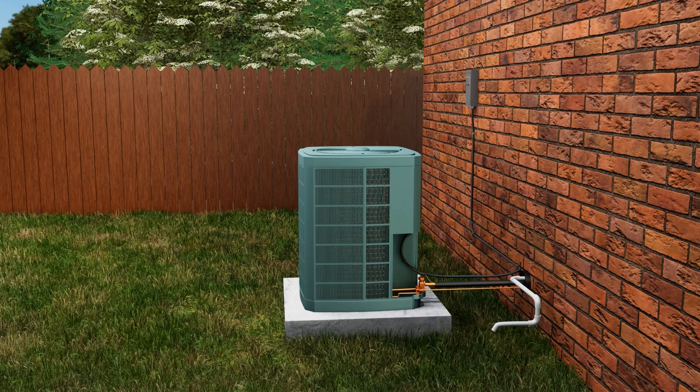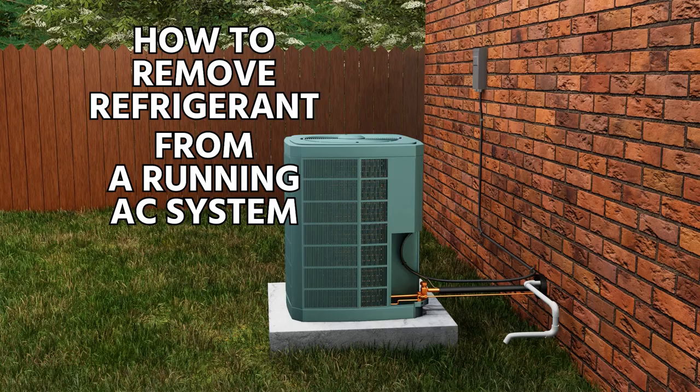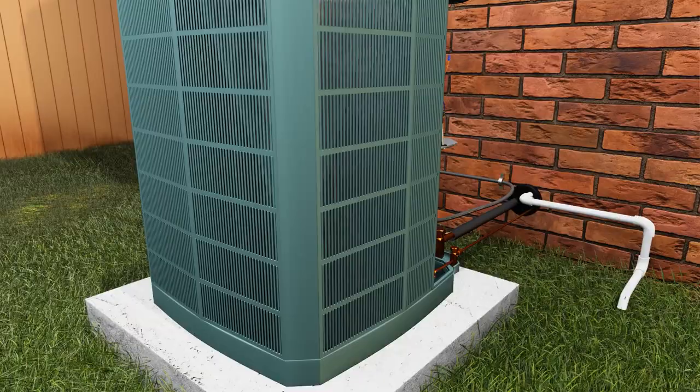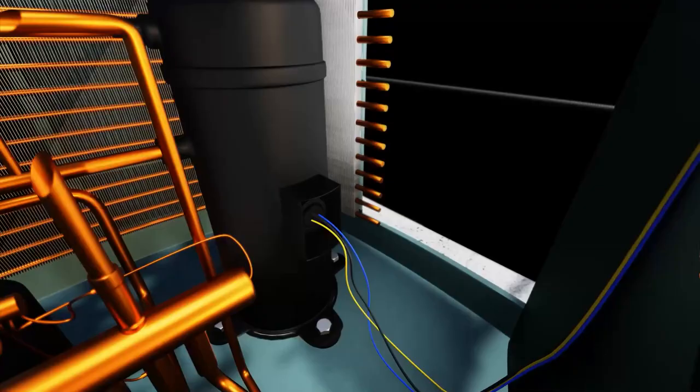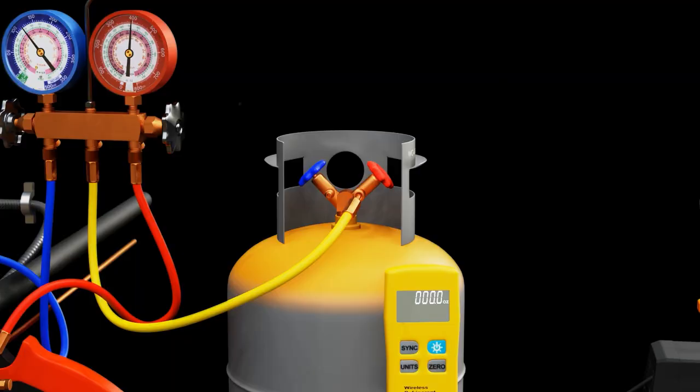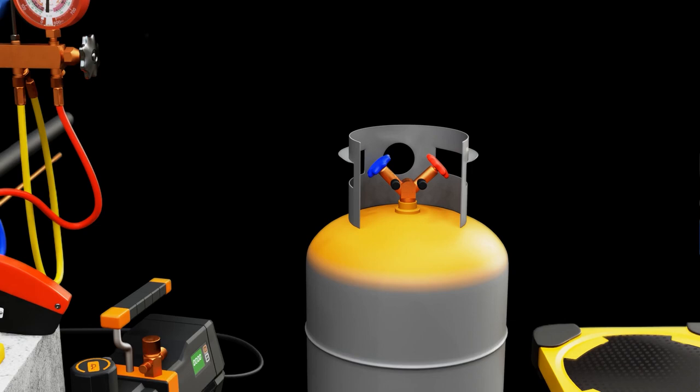This video is going to be about how to remove refrigerant from a running AC system. If you have a compressor that is operational, it's actually quite easy to get refrigerant out of the system, only to a point. You don't want to pull it down into a vacuum, but you can remove a good portion of the refrigerant very easily by just connecting from your liquid line to a recovery cylinder.